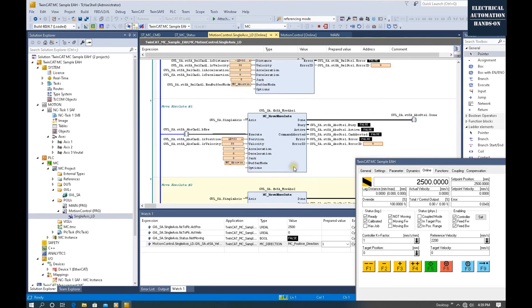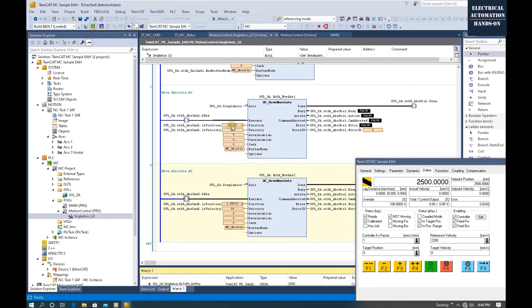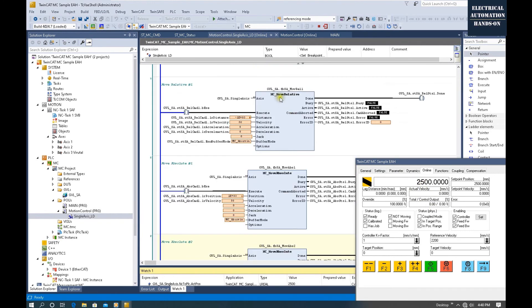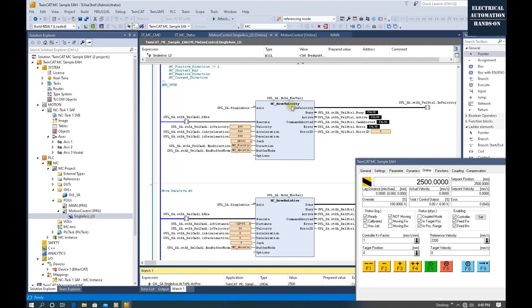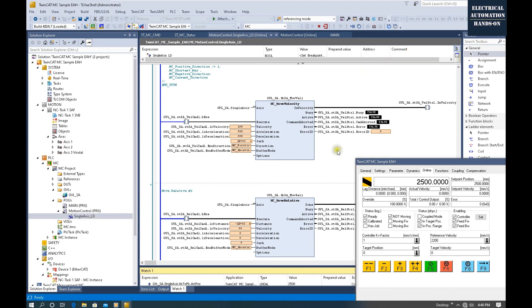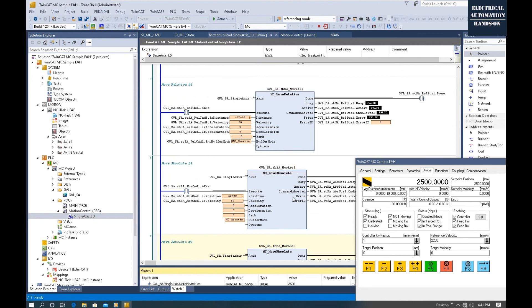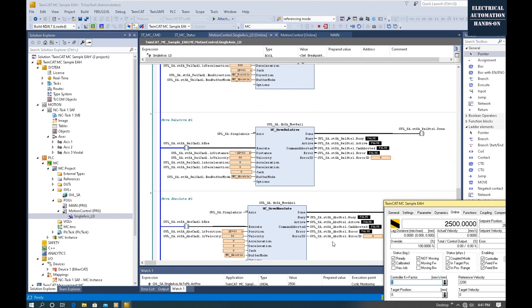This is the typical command set: Move Absolute, Move Relative, and Move Velocity — three common function blocks for motion control. Comparing these three commands: Move Absolute, once it finishes its job and reaches the target, the axis stops itself. Same thing for Move Relative — once it finishes the relative distance motion, the axis stops itself. But for Move Velocity, that is speed control — once we fire a rising edge on this function block, the axis keeps moving. To stop it, we need to use MC Halt or MC Stop. In the next video, I will show MC Halt and MC Stop. This programming style can be used as a sample or demo for you to practice your motion control.